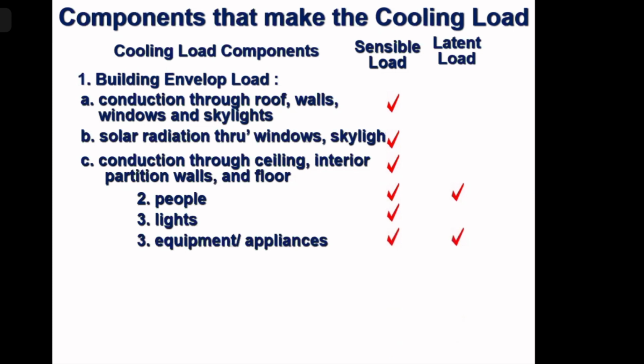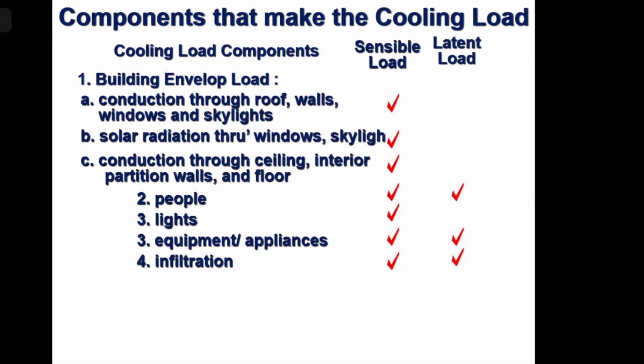It can give sensible and latent, mostly sensible if it is computers and control panels, etc. It is sensible, but if we use any equipment which also deals with water, then it may give out some latent heat also. Next. Infiltration air. If there is infiltration, outside air coming in means it will bring in both raw heat, sensible heat, and moisture, that is latent. Next.